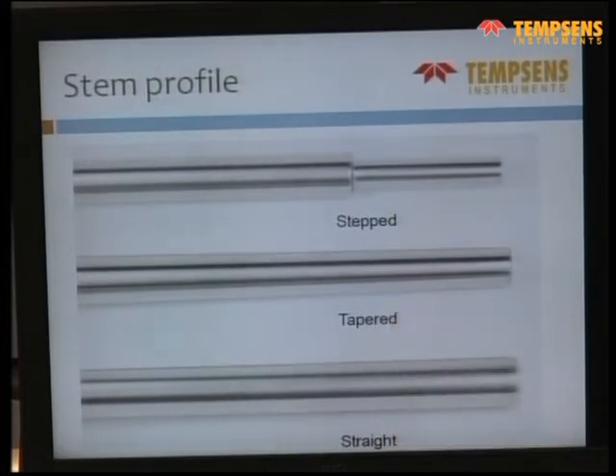In the case of a taper construction, you have a smaller bottom, which is the sensing portion. This gives a better response time than the straight construction. The advantage of straight construction is better pressure withstanding, or better life with aggressive materials, for example in a cement plant. There the importance is not response time but how much life you can get from the thermowell. A straight one has more material at the bottom, so it can give better life in such applications. It is always a balance between life and response time.